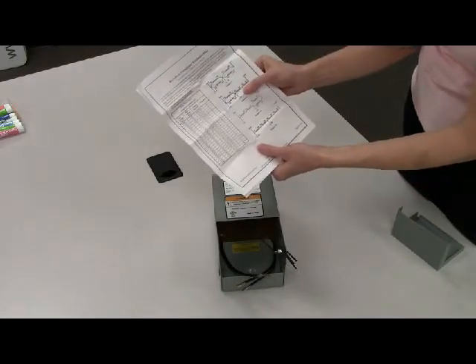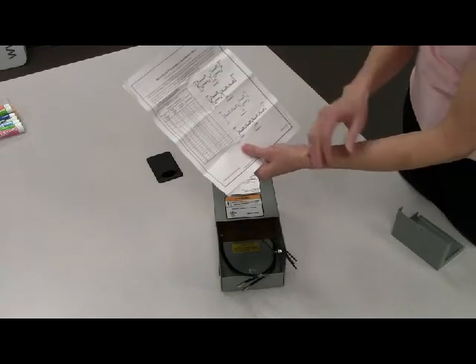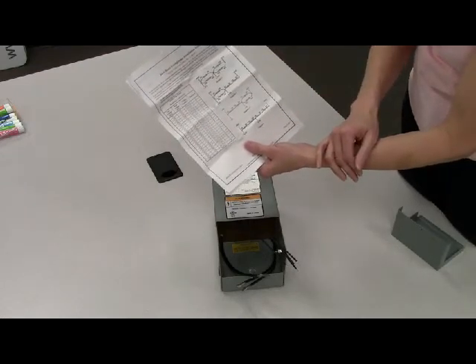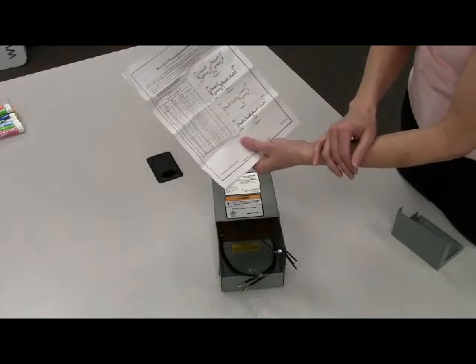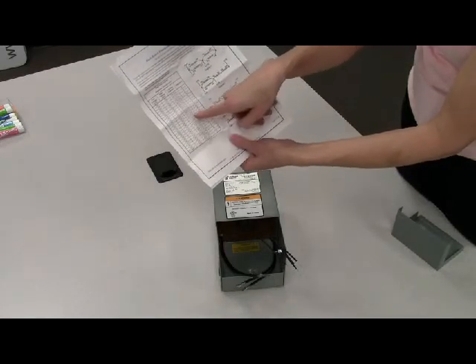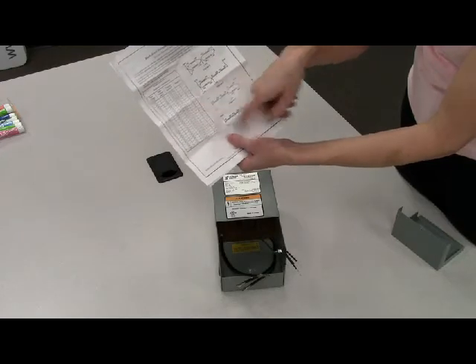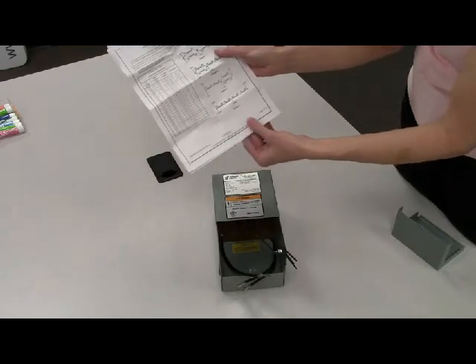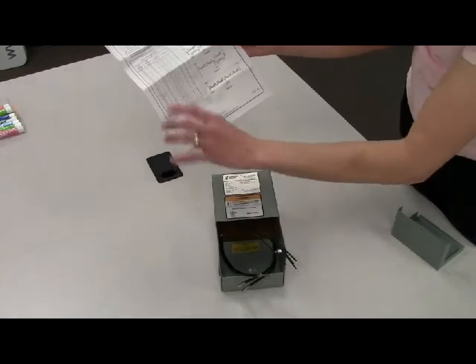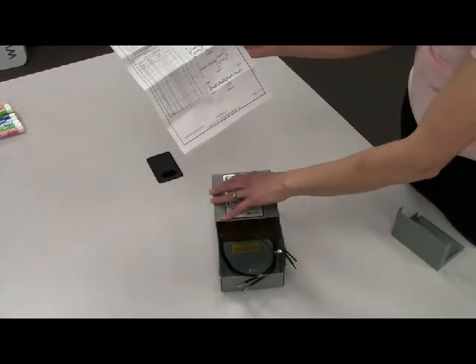So let's look at one scenario. Maybe you have 208 volts and you want 230 volts. There it is right there, and you go to your wiring diagram 4 and you can connect it to boost the voltage up. So now back to Brad's situation. He had a 230 volt pump and he had 208 volt three-phase available. So let's see if we can use this transformer.